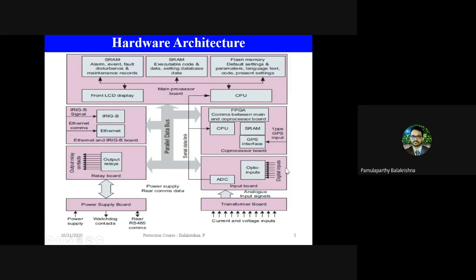Okay. So apart from that, there are analog inputs. The sinusoidal currents and voltages are one kind, whereas the analog inputs that I am referring to here are any signal like temperature, pressure, or anything that is measured by a transducer, a sensor, or an RTD. All those inputs are also connected to the relay as analog inputs, but they usually come as either 4 to 20 milliamp signals or a change in resistance, such kinds of signals.